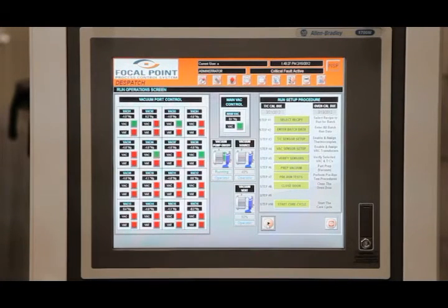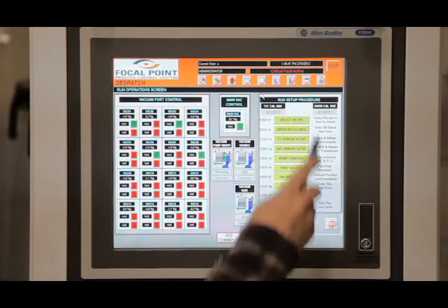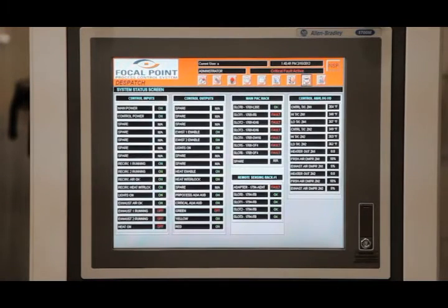Vacuum and heating systems are activated and the batch data file begins recording. During the curing process, the operator can check the system status screens for detailed information. The system monitors the pressure in each of the vacuum lines and alarms if pressure in any of the lines drops below a predetermined level.